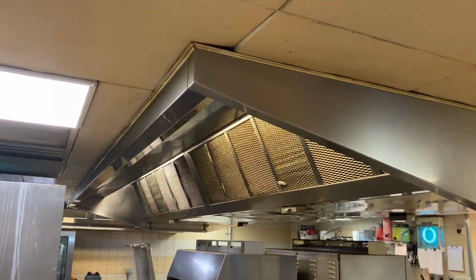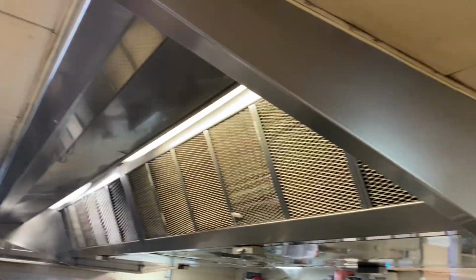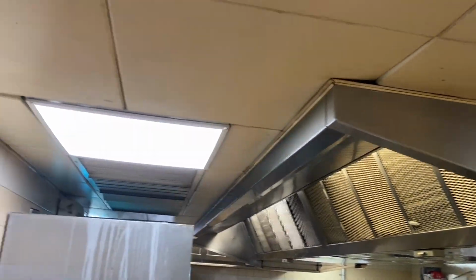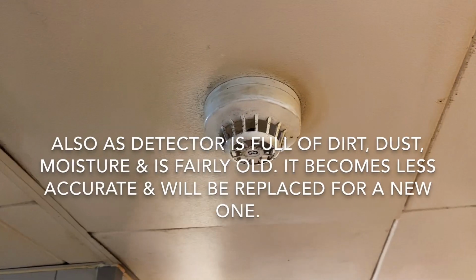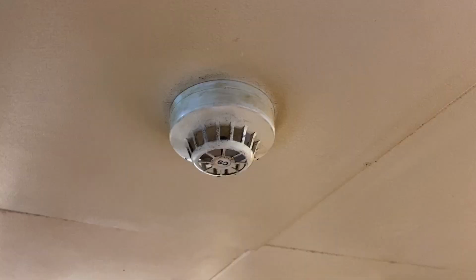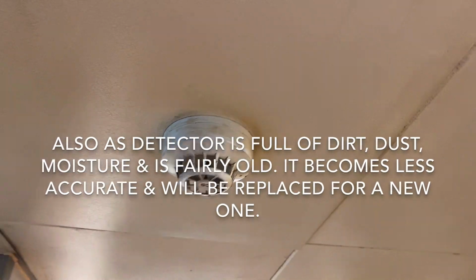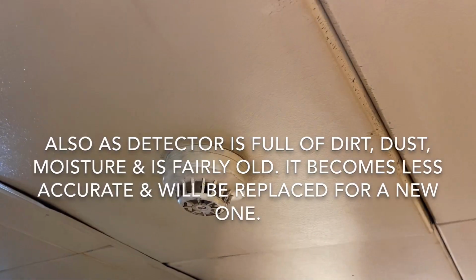Another thing, this device here is very hot. When you put your hand up, it is hot enough to have triggered the other situation that happened here with a fire fault. I've let the customer know that this is going to have to be relocated soon, considering it's going to keep causing false alarms.